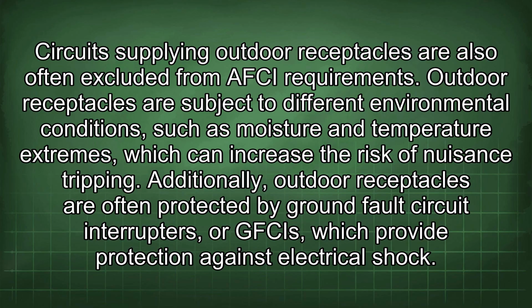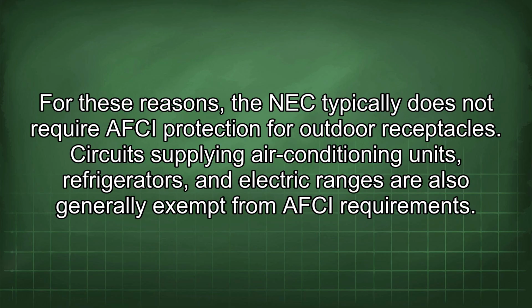Circuits supplying outdoor receptacles are also often excluded from AFCI requirements. Outdoor receptacles are subject to different environmental conditions, such as moisture and temperature extremes, which can increase the risk of nuisance tripping. Additionally, outdoor receptacles are often protected by ground fault circuit interrupters, or GFCIs, which provide protection against electrical shock. For these reasons, the NEC typically does not require AFCI protection for outdoor receptacles.